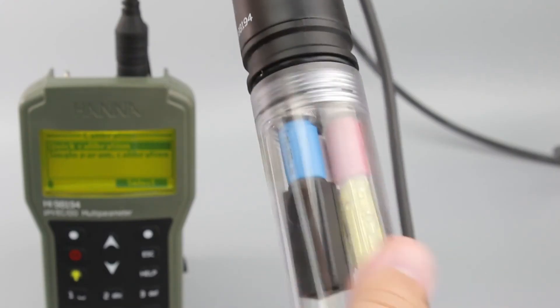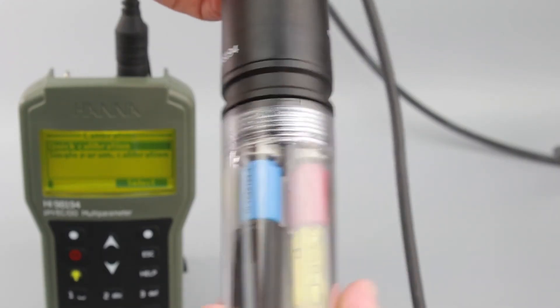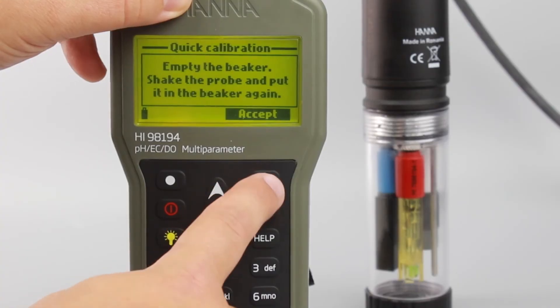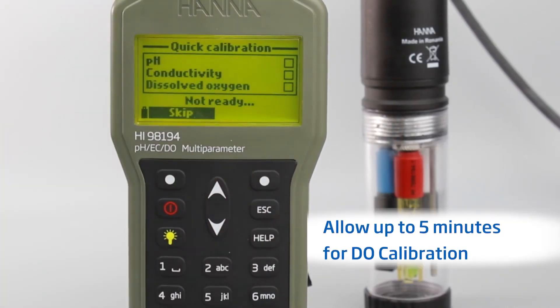No droplets should remain on the DO sensor tip. Screw the empty calibration beaker back onto the probe body. Press Accept, and then press Confirm to finish calibration.